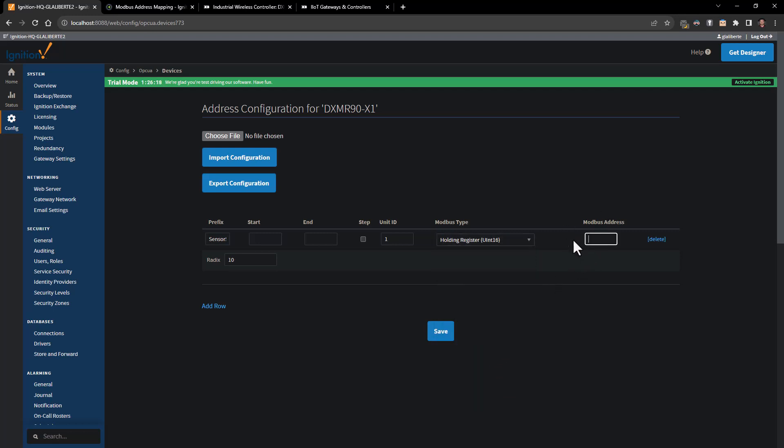The Modbus address is going to be that starting Modbus address that we're going to be pulling from. In the DXM world, we've got one through eight thousand our local registers. Typically for holding registers they would start at forty thousand, but because Ignition recognizes this as a holding register already, it drops the forty thousand as does the DXM. So register one on the DXM is register one in the Ignition software.